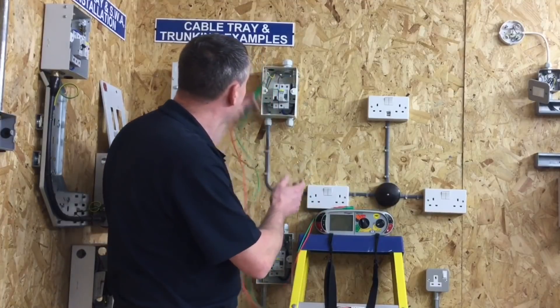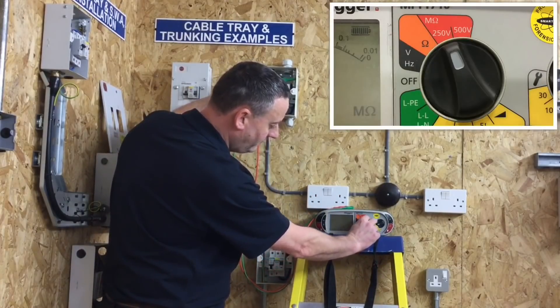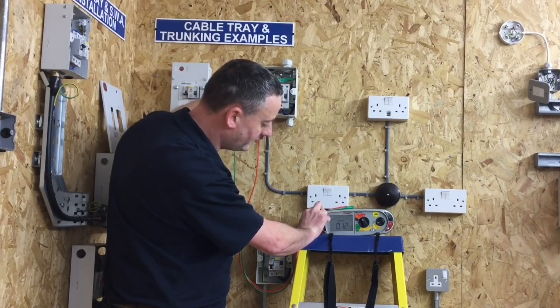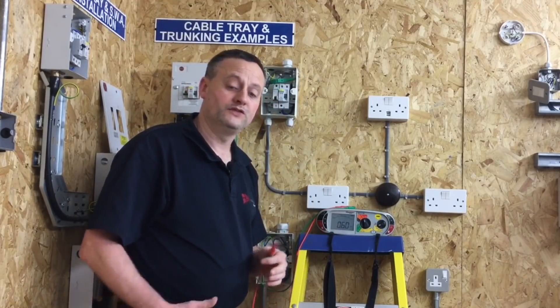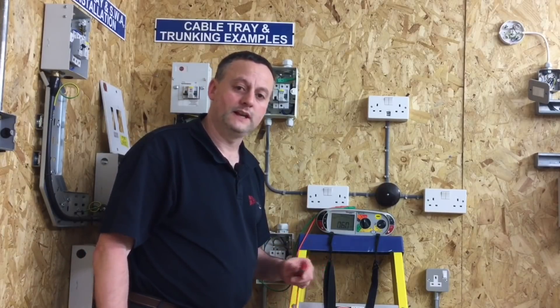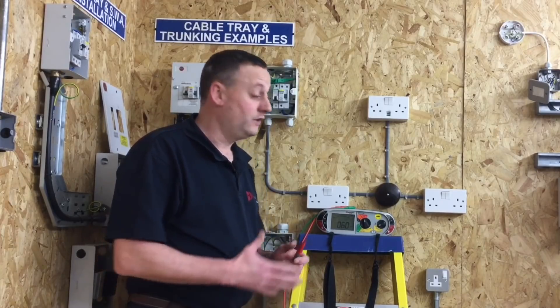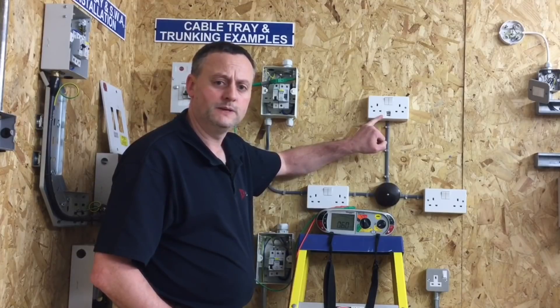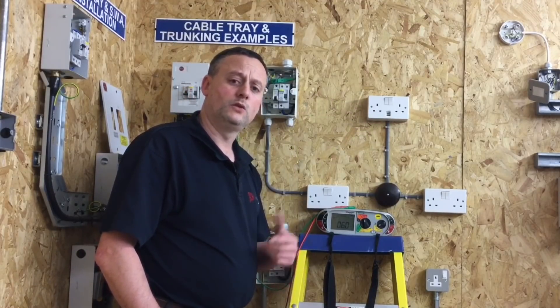Insulation resistance should be done at 250 volts where we're unsure of equipment in circuit. Testing between the neutral bar and the top of the breaker, I set my instrument to 250 volts and carry out the insulation resistance test. We can see once again we have picked up the permanently connected electronic components, and our reading is less than one mega ohm. What we have proved, however, is that there isn't a dead short — so when energized it would not trip the overcurrent protection, but something is in circuit.